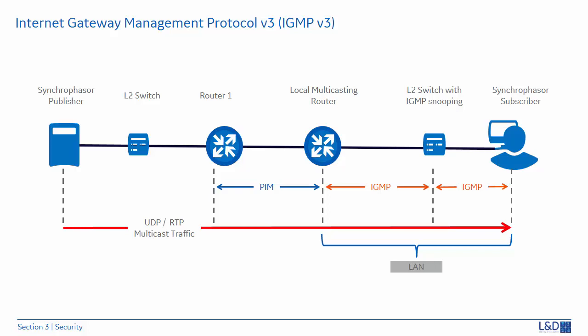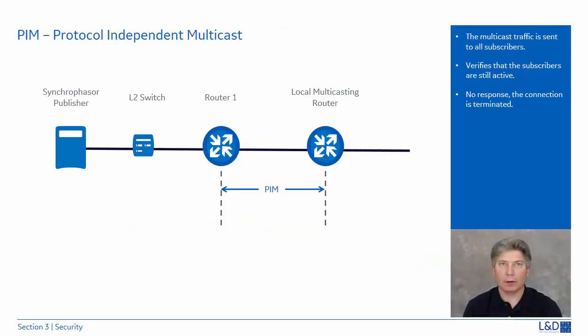IGMP version 3 operates within the substation's LAN to the local router observing the IGMP traffic. To ensure the subscribers are still active, the local multicasting router notifies the subscriber to confirm whether the subscriber is still online. If there is no response from the subscriber, the communication link is broken. A protocol called Protocol Independent Multicast, also known as PIM, monitors the networks to make sure that the subscribers are still requesting data. It has an automatic breakdown feature, which means it will drop the link to a specific subscriber if the requests stop.